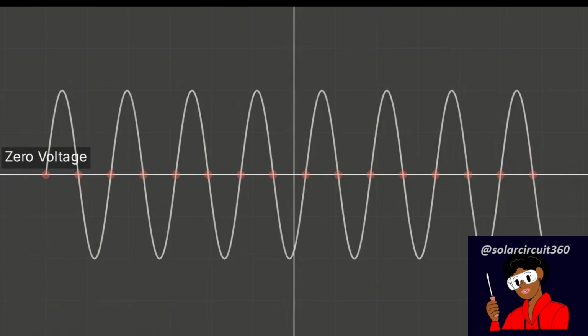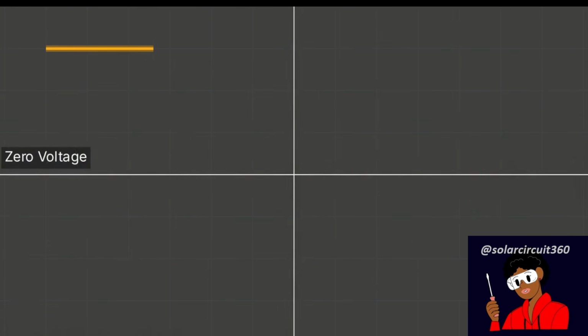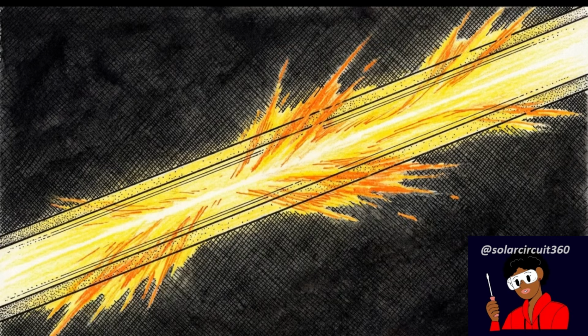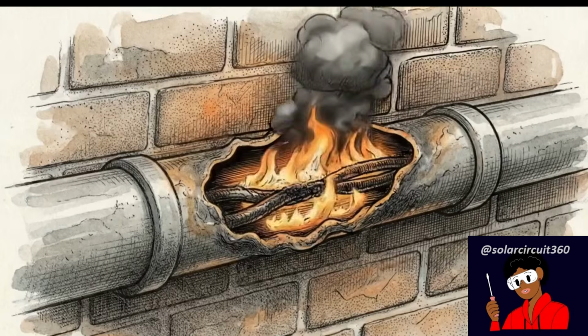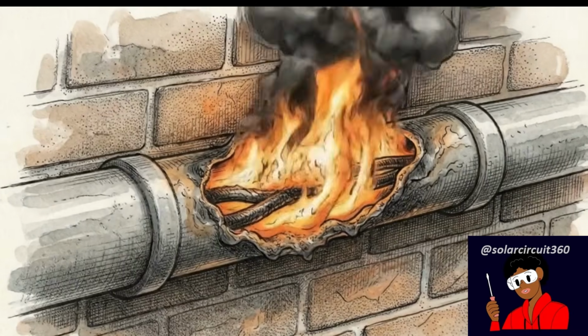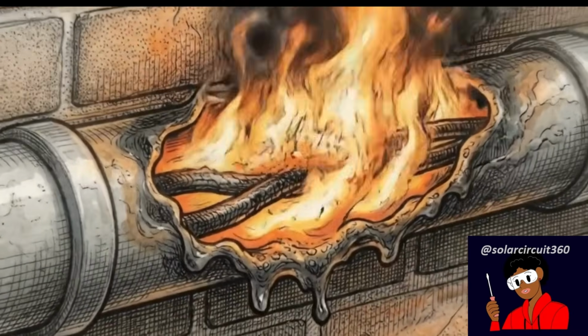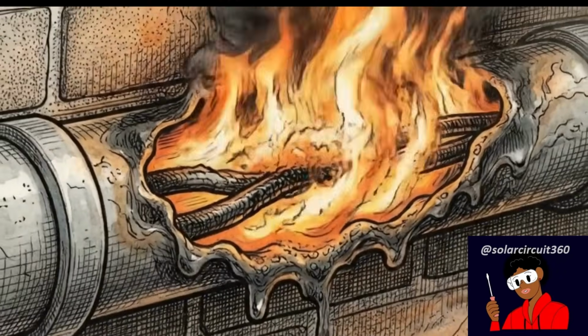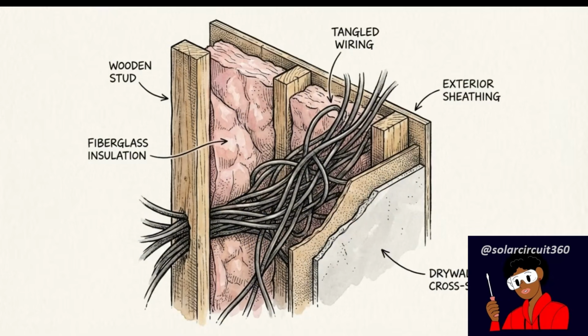But solar arrays produce direct current. Notice how the voltage flows as a flat, relentless horizontal line. Direct current completely lacks a zero crossing to break the circuit. Because DC power never drops to zero, the physics of the system actively feed the flame. It allows the arc to sustain itself continuously until the physical material of the wire and conduit is entirely destroyed. When that sustained arc is trapped inside a wall space or a conduit run, the physical consequences escalate rapidly.